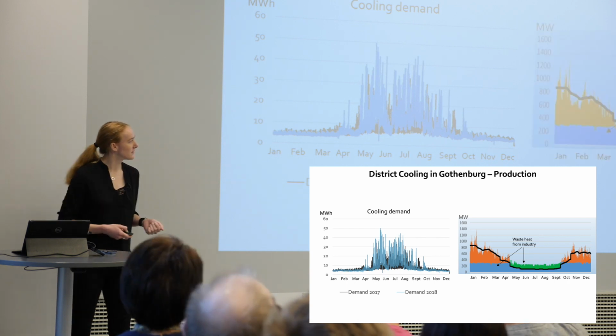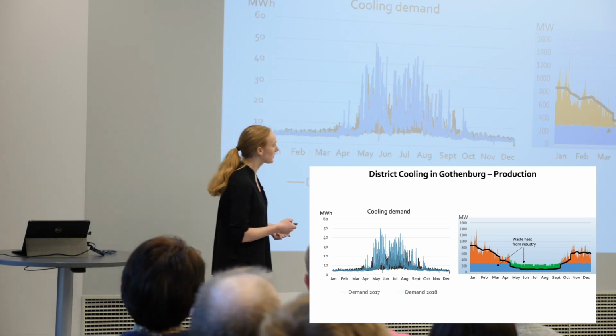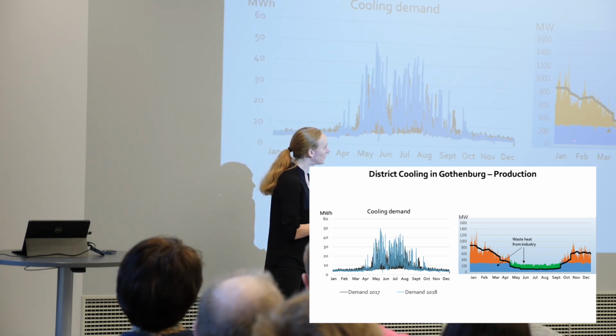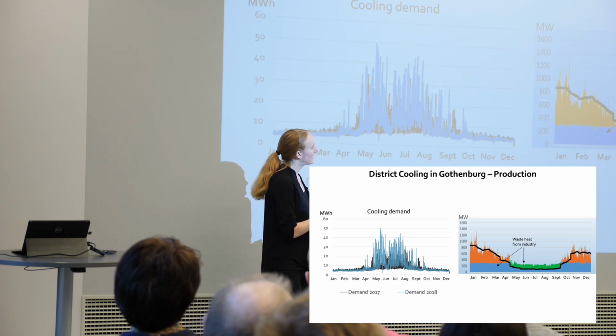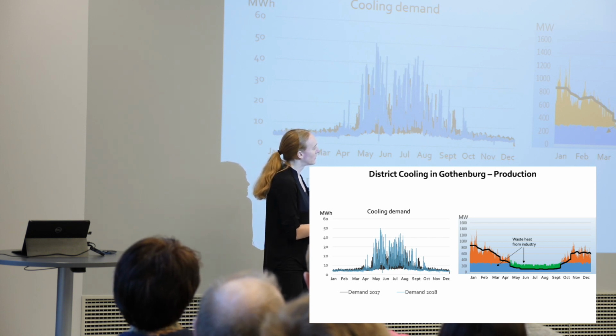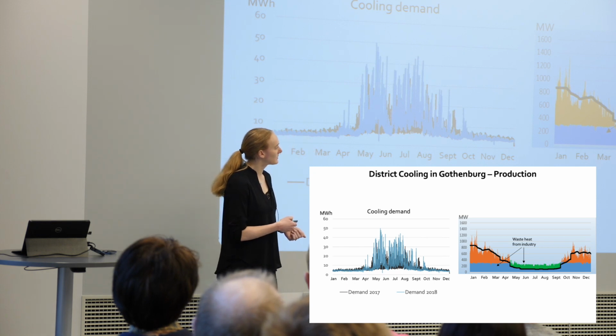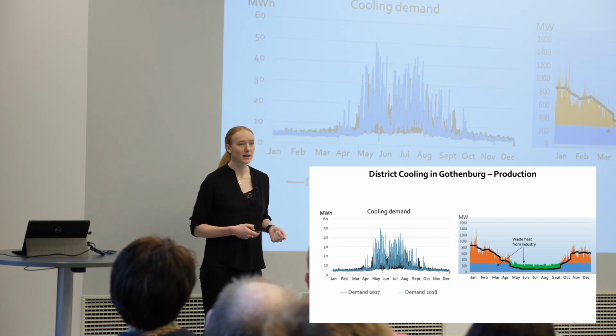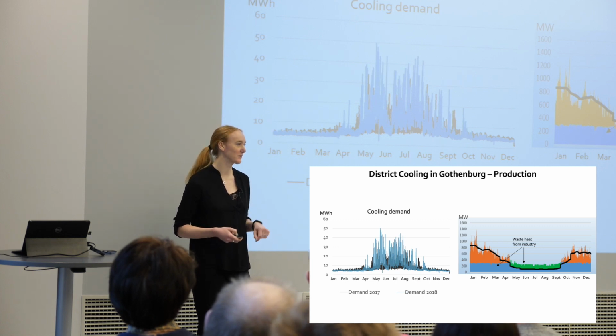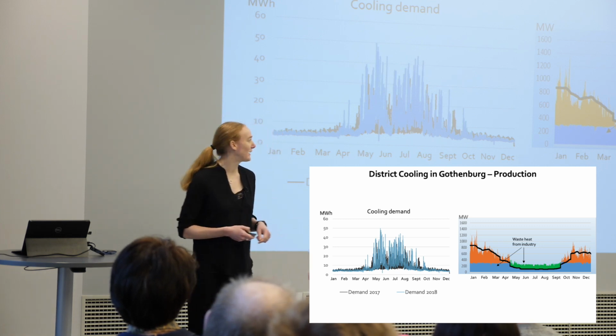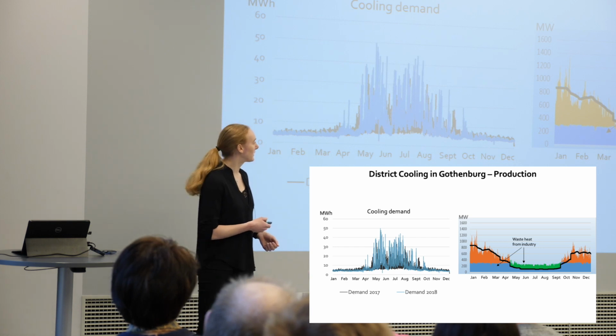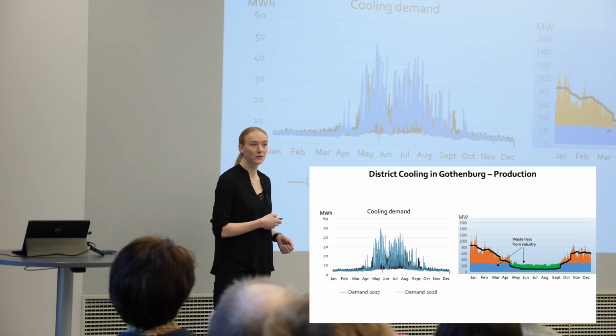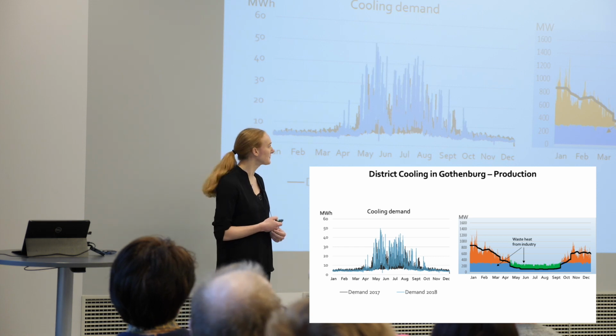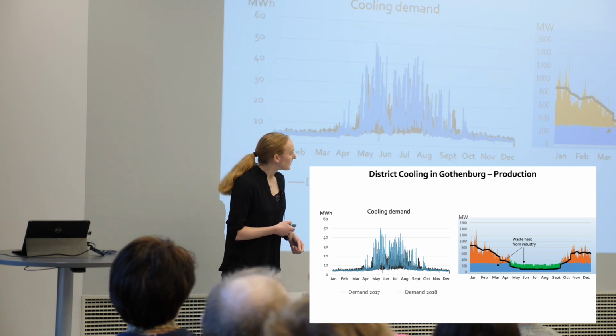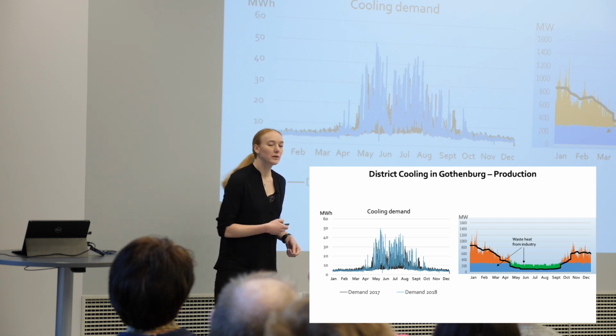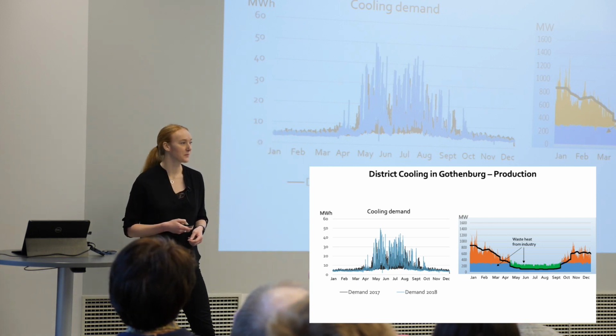And back to the absorption chillers, so the waste heat is what you can see here in the green and also the blue. This is throughout the whole year. And the heat demand is this black curve here. So in the summer, there's a lot of waste heat, the green area here, that would otherwise have to be cooled away to the birds by cooling towers and so on. So that's why it's very good to use the absorption chillers to take care of this excess waste heat. And the waste heat is close to 300 megawatts during the summer.